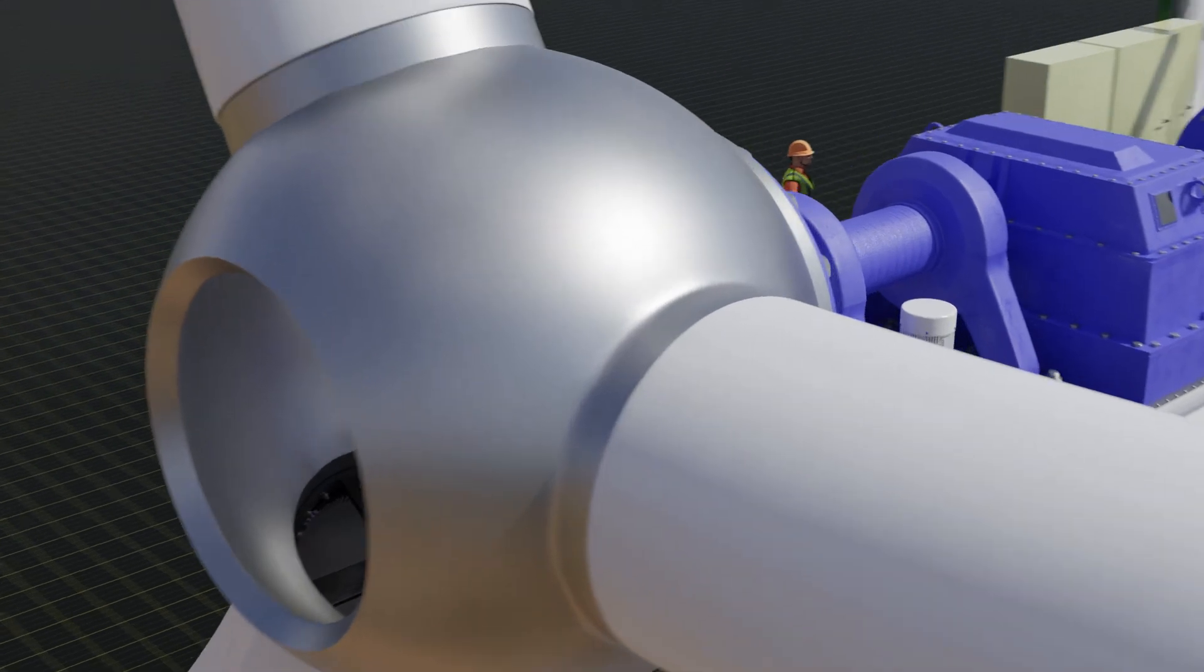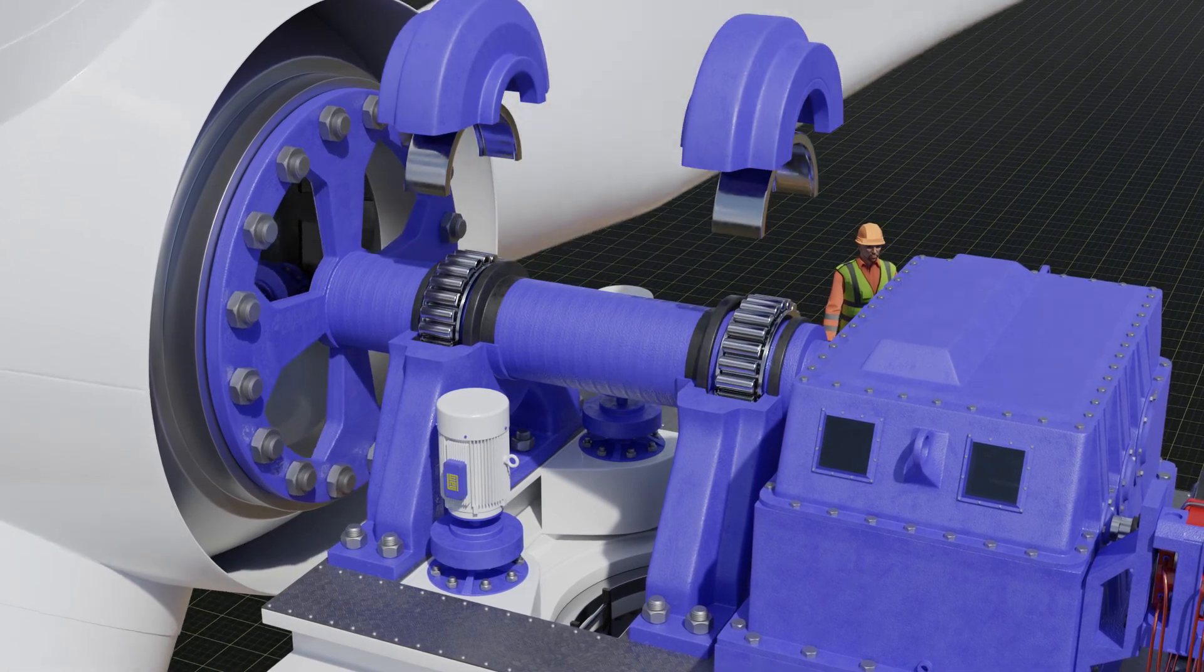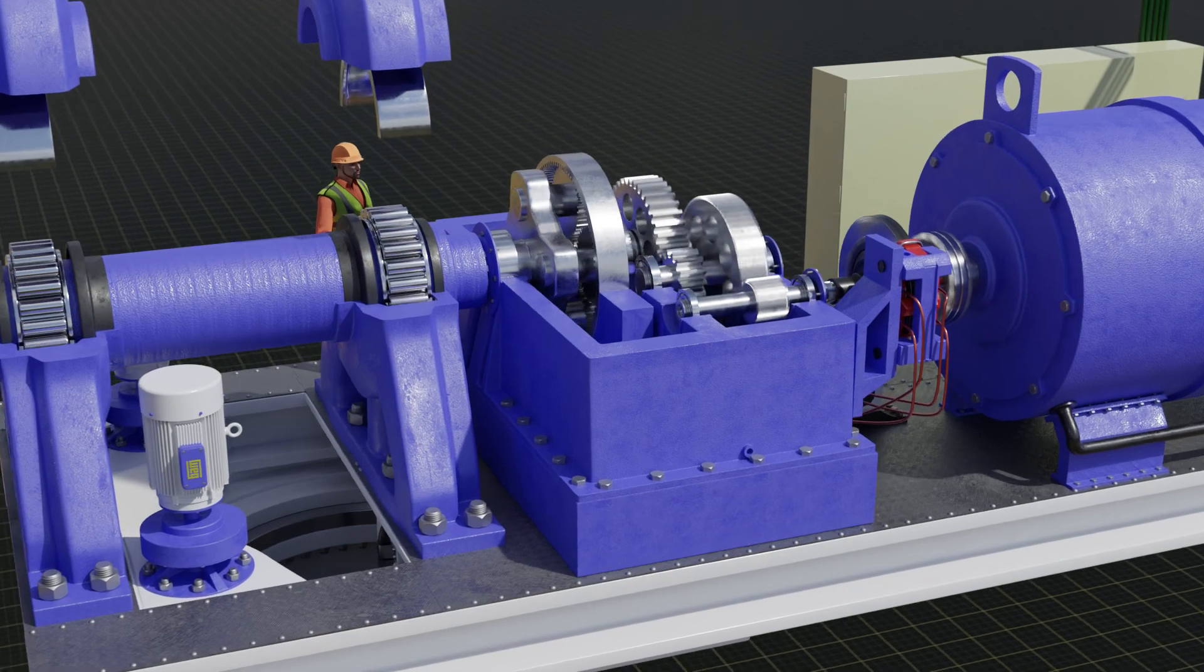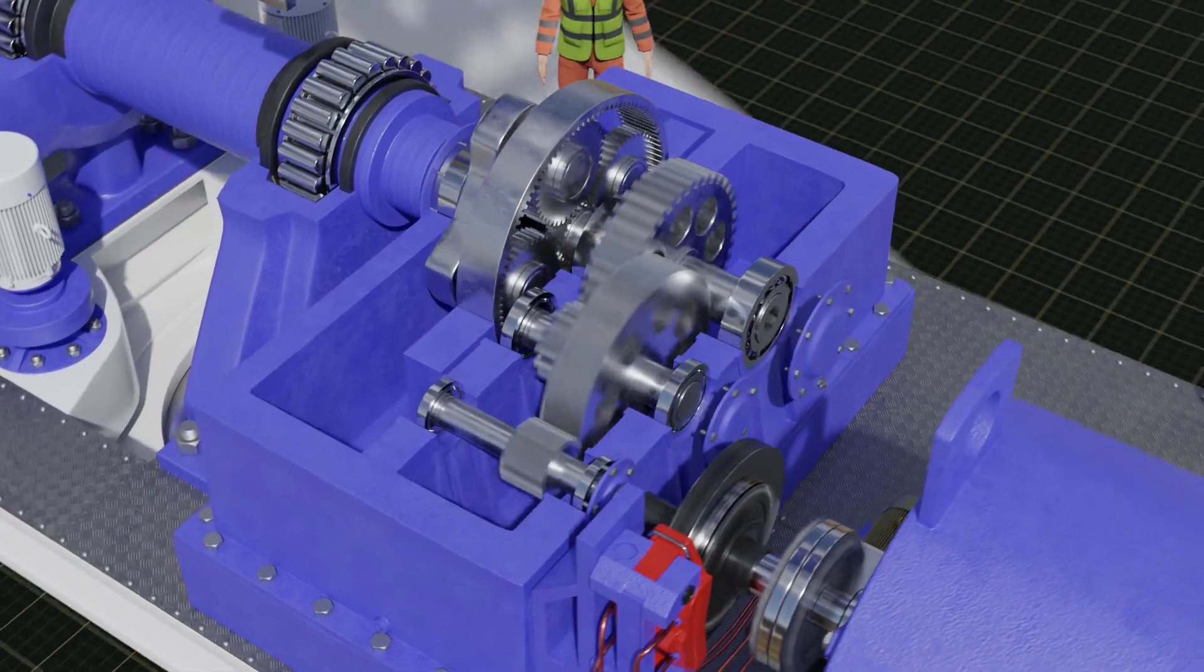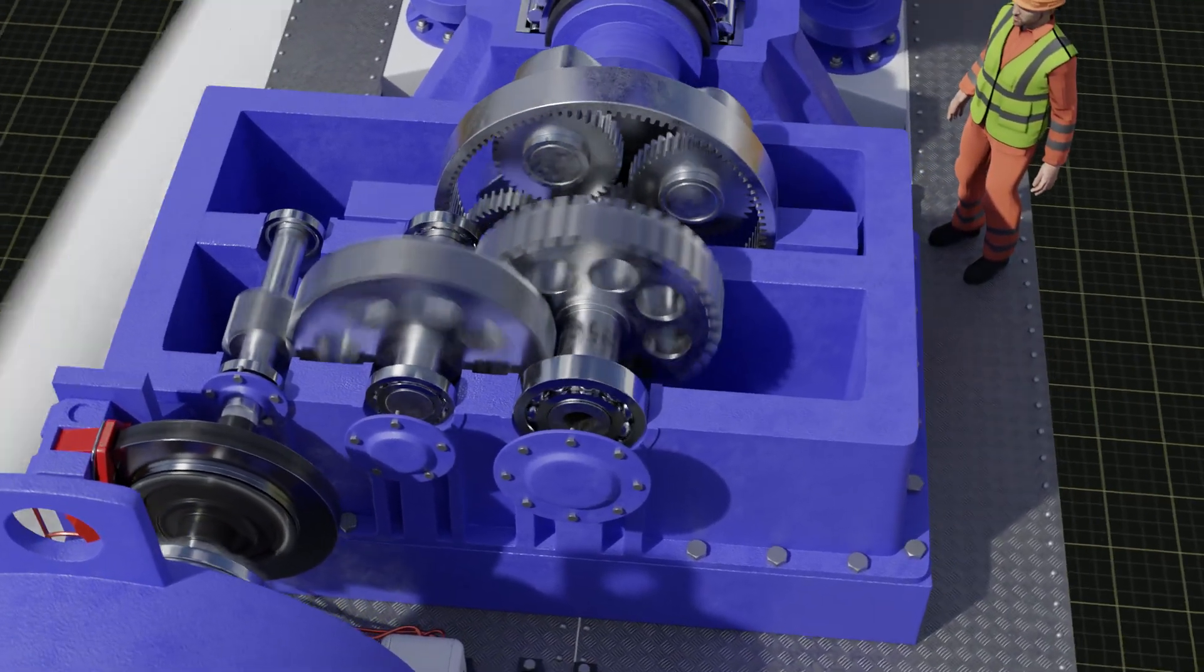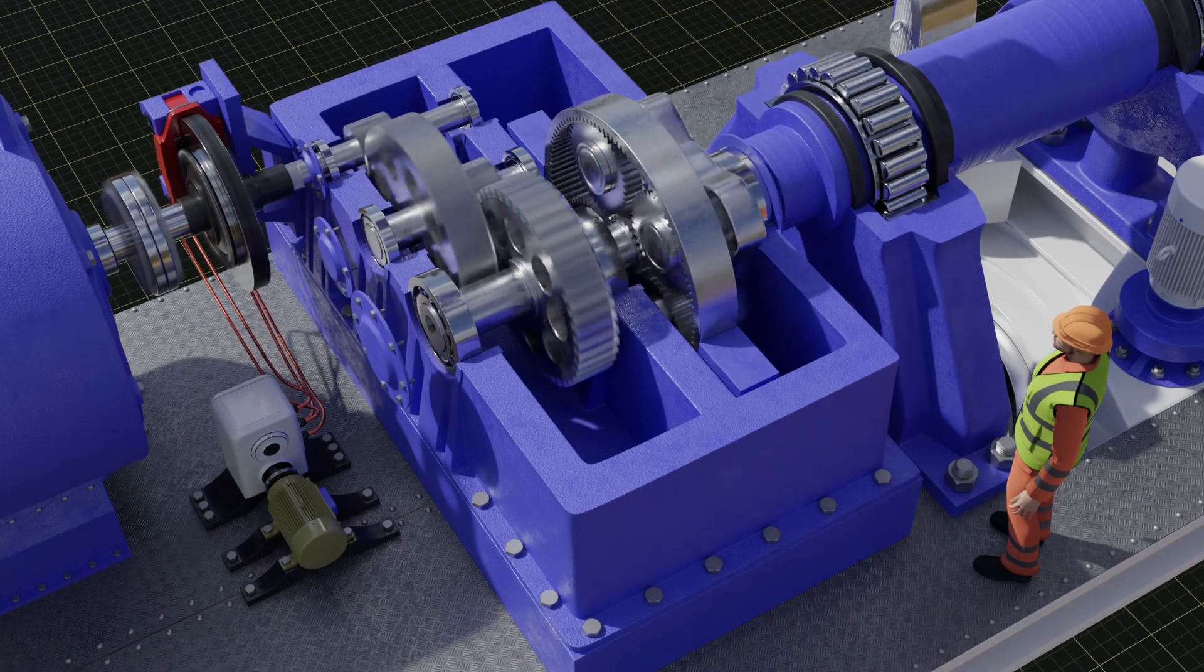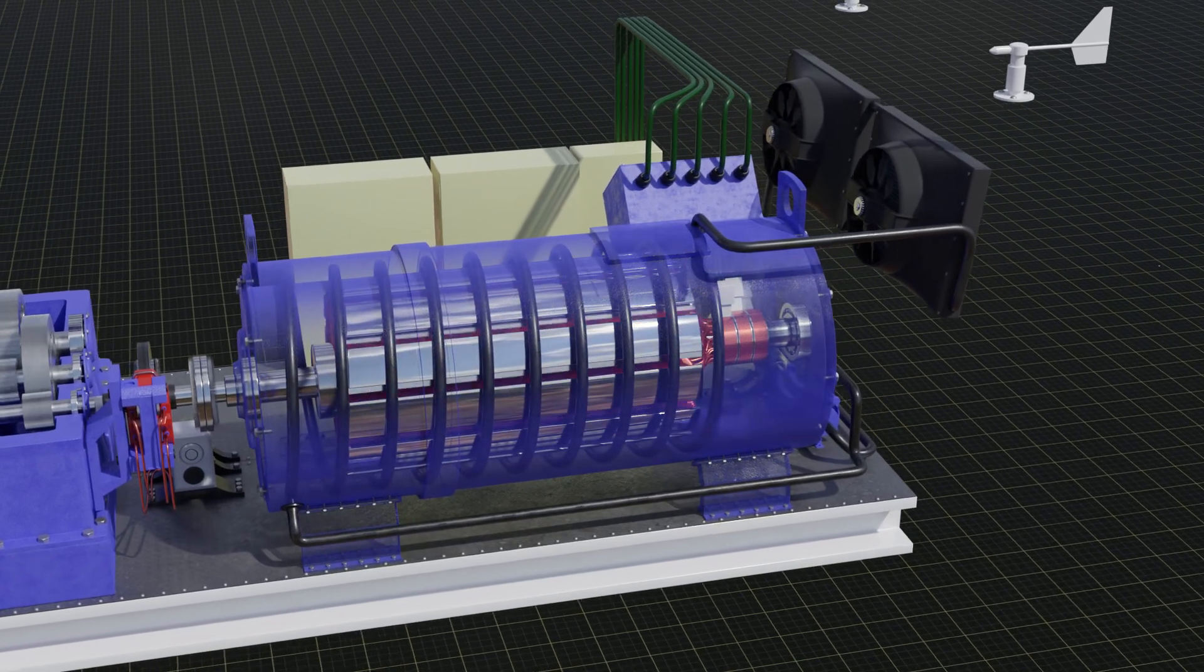The hub is made of metal, and the turbine main shaft is attached to it. This shaft is attached to the frame through two large bearings. The shaft is connected to a gearbox. This gearbox increases the number of revolutions per minute. The turbine's main shaft rotates at about 12 to 17 revolutions per minute. The gearbox increases this number about 100 times. As a result, the shaft coming out of the gearbox rotates at about 1,500 revolutions per minute. The output shaft turns a large generator that generates electricity.